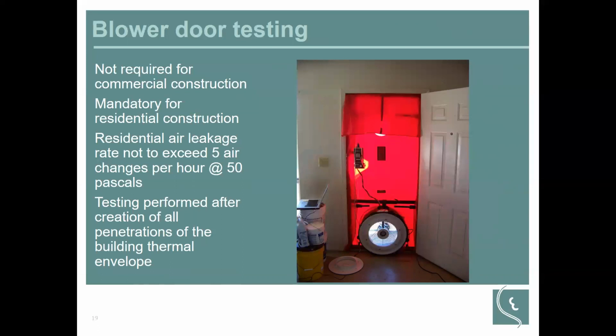It is not required for commercial construction, although some commercial buildings are doing that these days, but it is mandatory for residential construction. And the residential air leakage rate cannot exceed 5 air changes per hour at 50 pascals. And the 50 pascals is the equivalent of about a 20 mile per hour wind hitting the side of your building. So you do this after you've performed all the penetrations of the building thermal envelope.